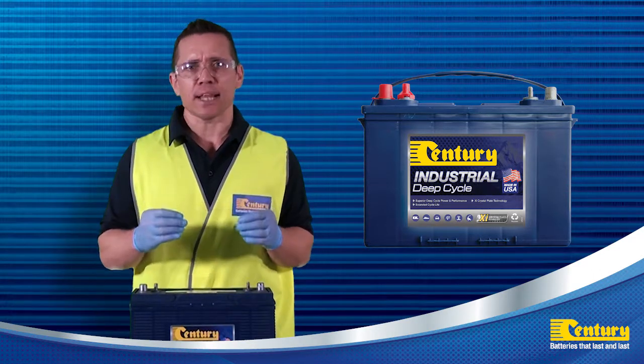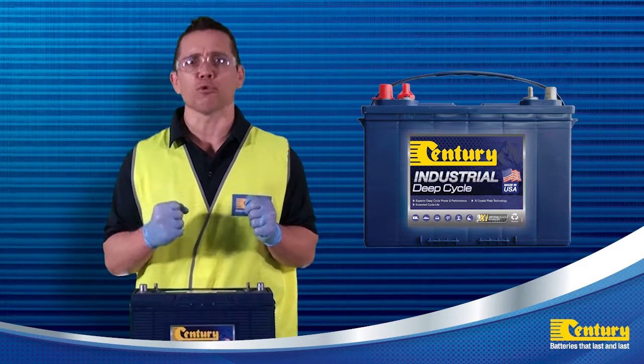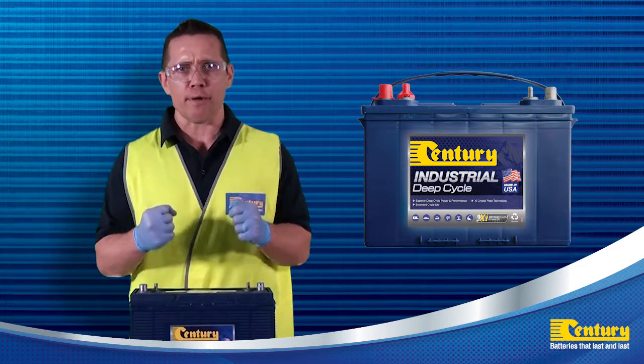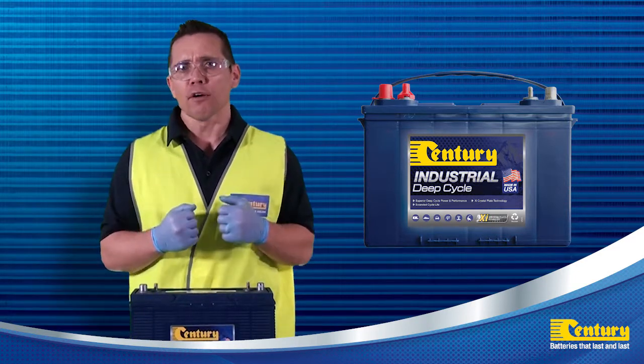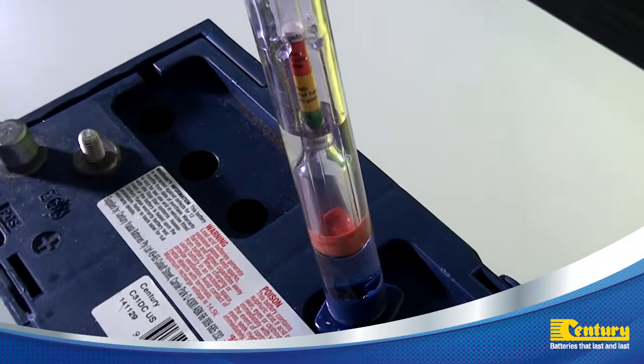Correct battery charging plays a key role in reaching peak performance and service life out of your Century Industrial Deep Cycle batteries. If you find the specific gravity readings are out of balance and cannot reach the specific gravity of 1.265 to 1.280, an equalisation charge may be required.